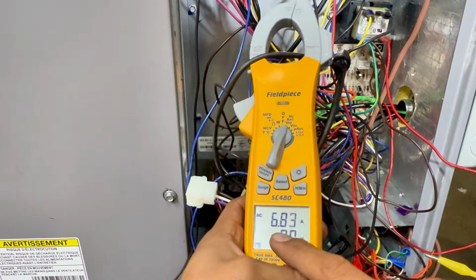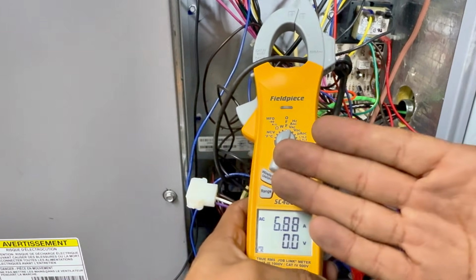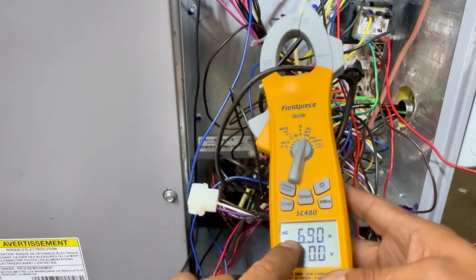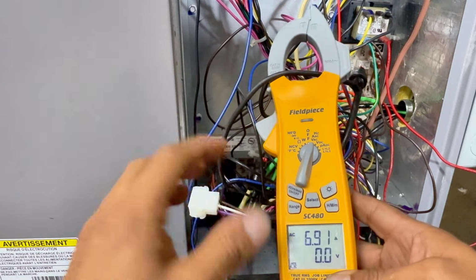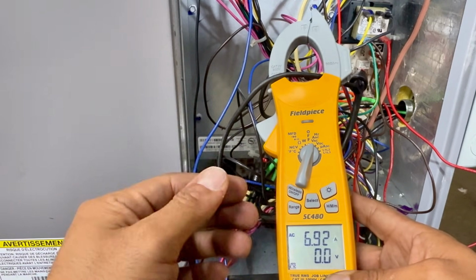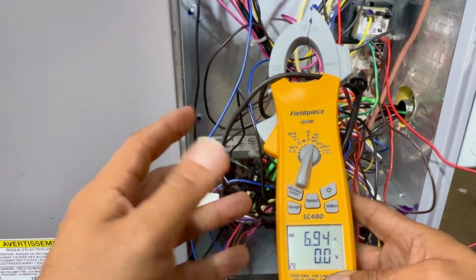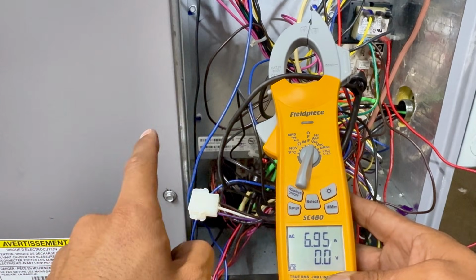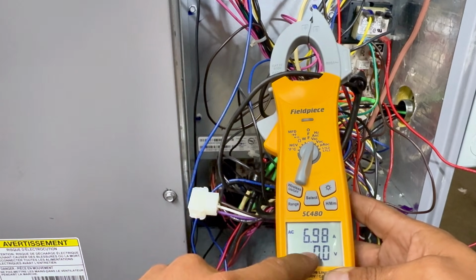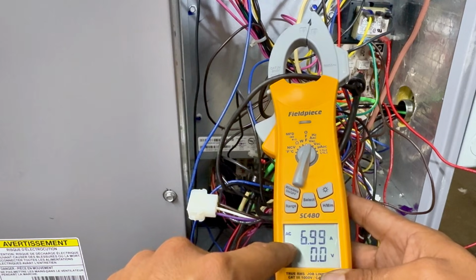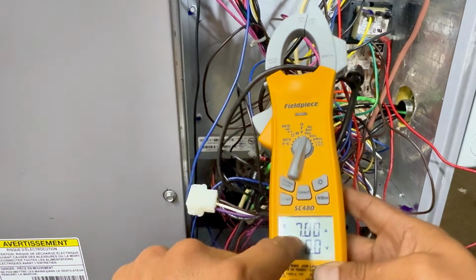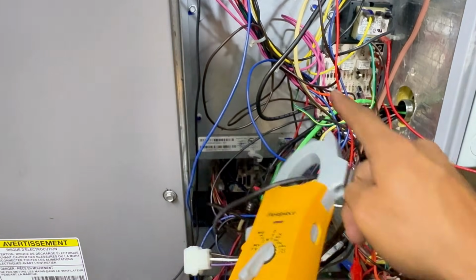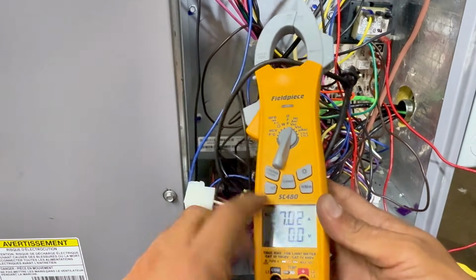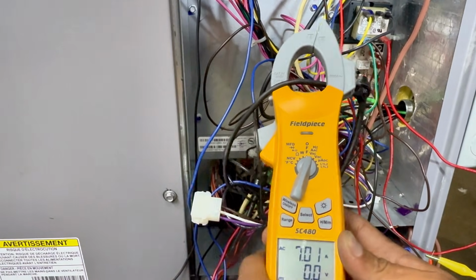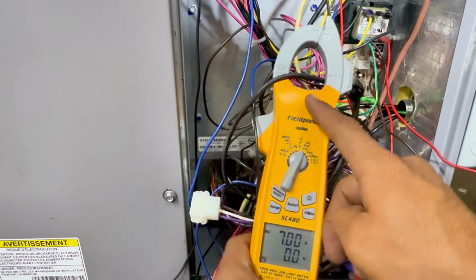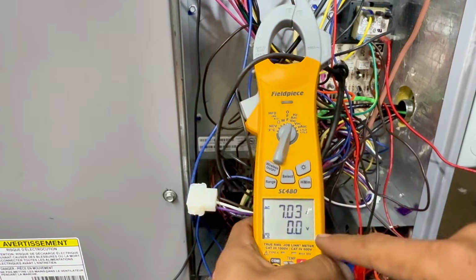But you see, I'm getting a sum of different loads. So I think the compressor was at 4 point something. My condenser fan motor was at 0.6. And my indoor motor was at 1.8. It kind of makes sense. I'm close to 7, right? So it's giving me all the loads. So by checking that one leg, the one that goes to common, it basically is adding up all my loads, how much current it's all pulling.